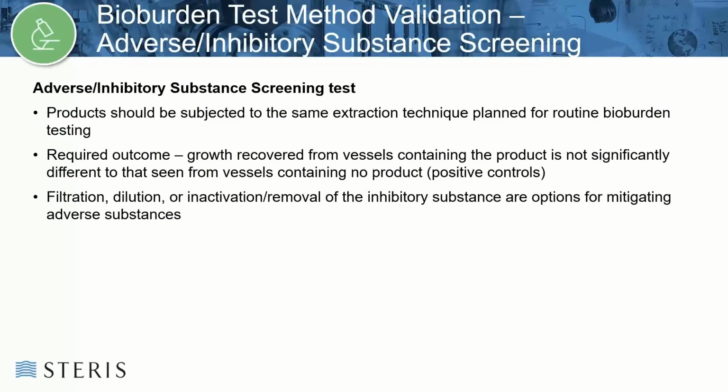Adverse screening for bioburden test method suitability ensures that the product or substances present in the product do not impact microorganisms in the test extraction or growth media, and thus create a falsely low measurement of contamination on the device.